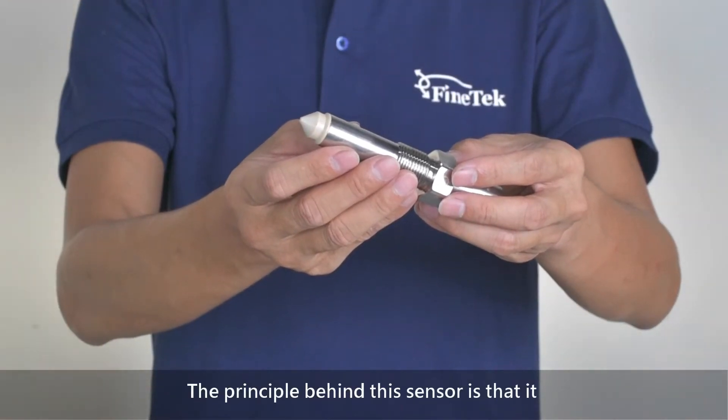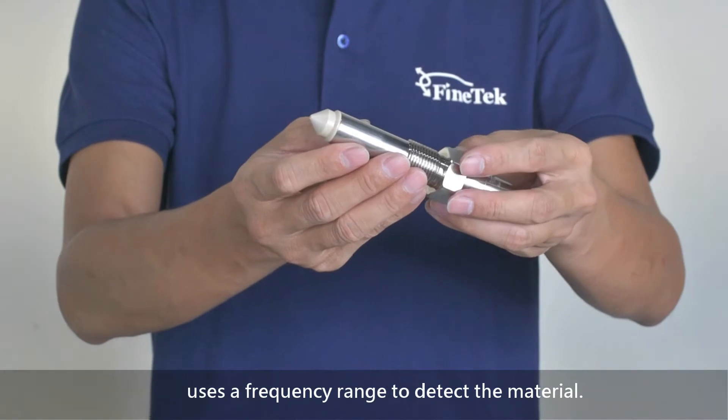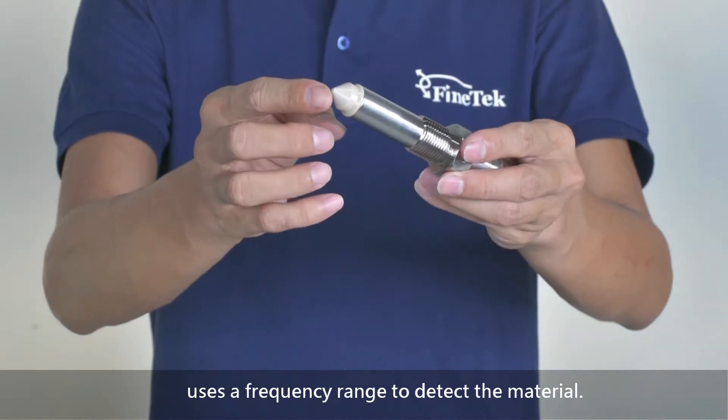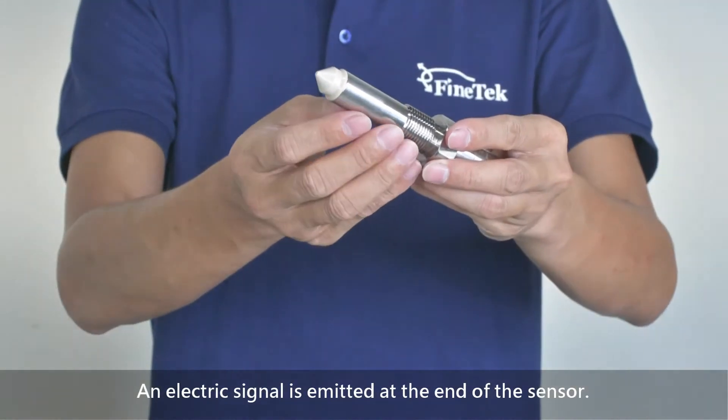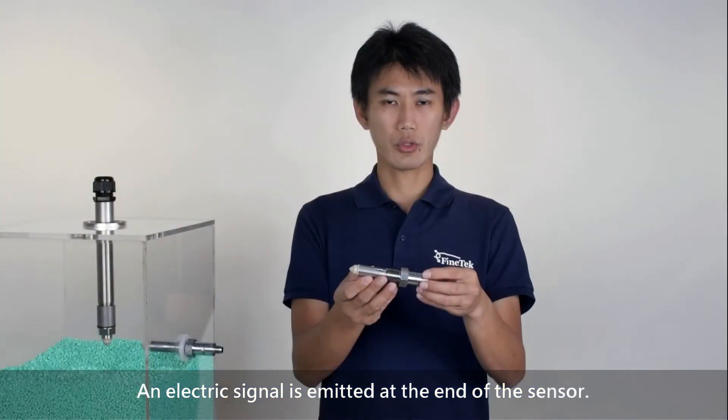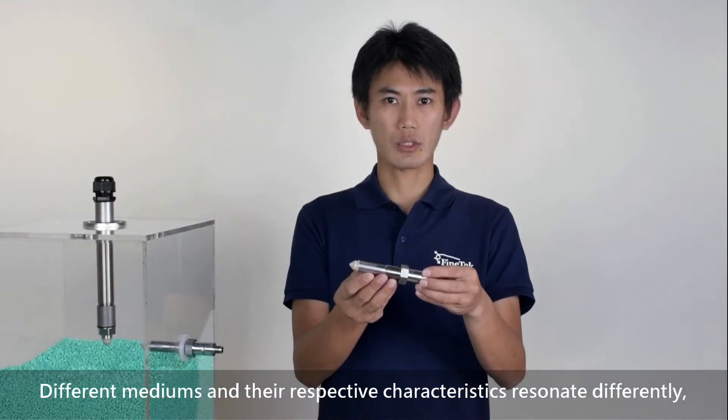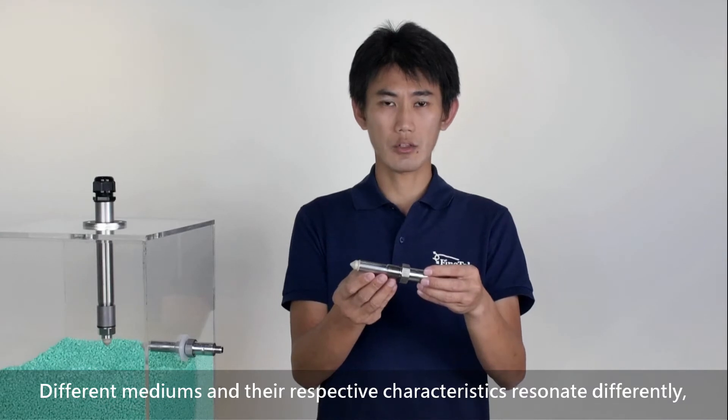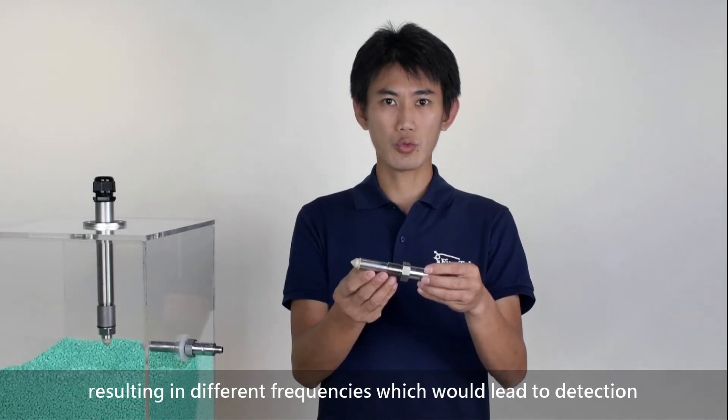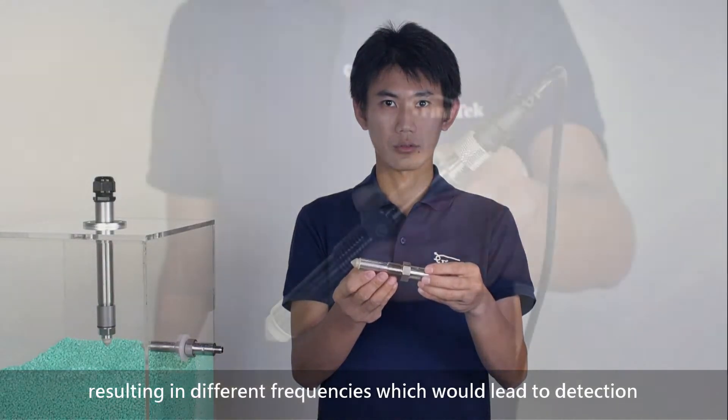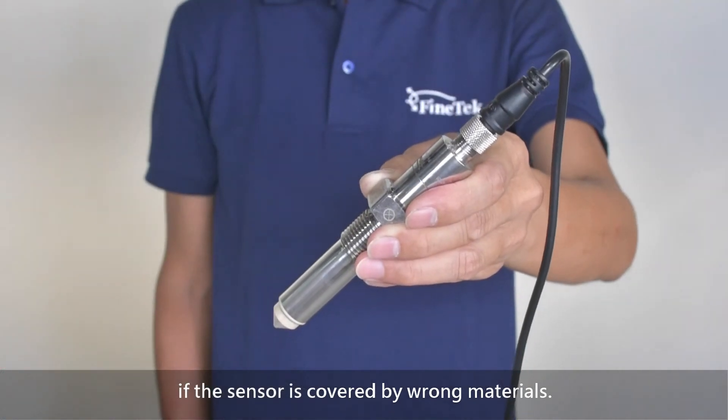The principle behind this sensor is that it uses a frequency range to detect the material. An electric signal is emitted at the end of the sensor. Different mediums and their respective characteristics resonate differently, resulting in different frequencies which lead to detection if the sensor is covered by material.